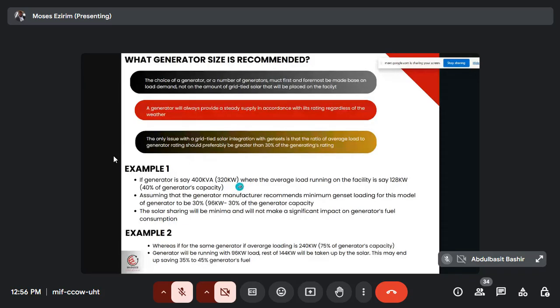Do you understand this? The generator capacity is 320, and the average load is 128. That is 40% of the generator capacity. The 30% recommended by the OEM is 96. Now, 128 minus 96 is what? 32. You can see that it's small. 32.